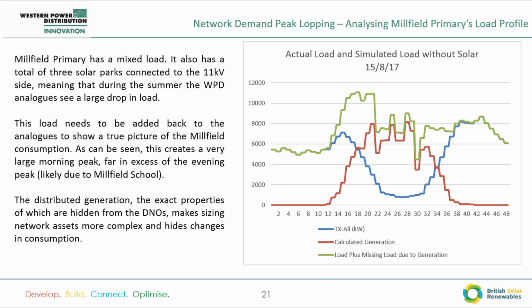So the blue line is the raw WPD analogs. That is what they see on their system as load during the summer day. Then the red line is our calculated generation, and thus the green line is what we're expecting the consumption from Millfield to be. So you're getting a very big morning peak there.